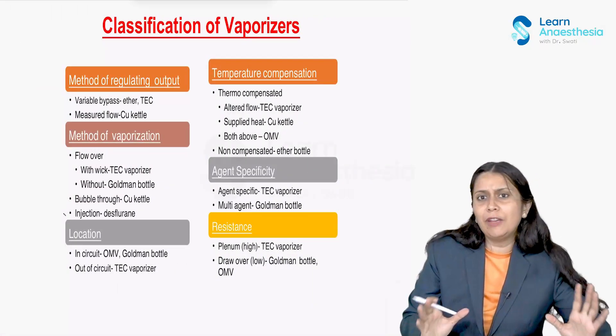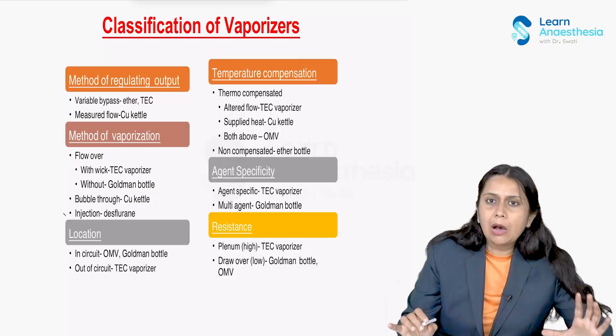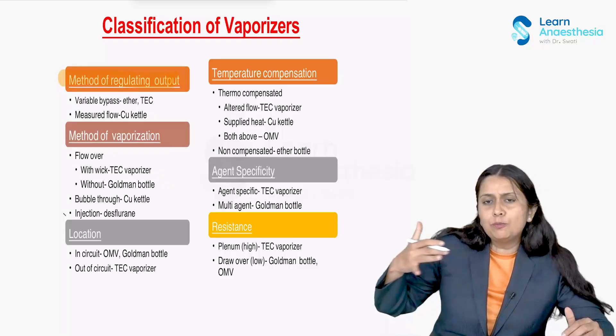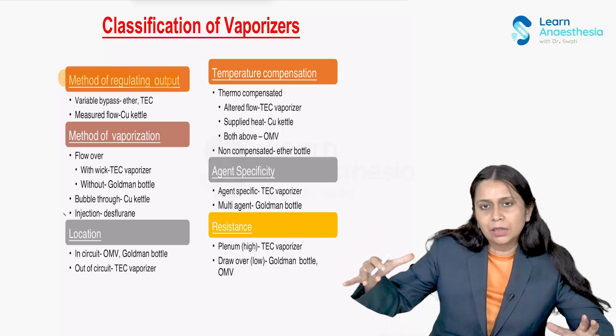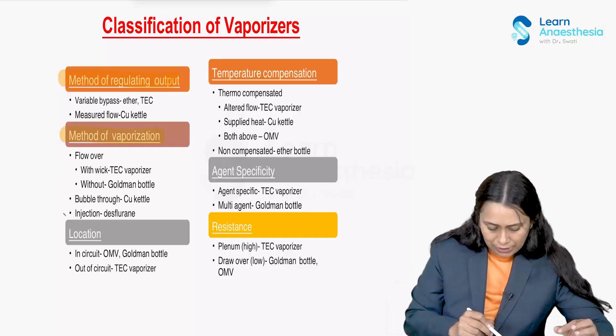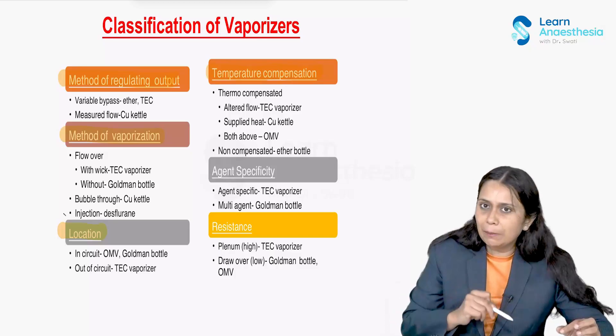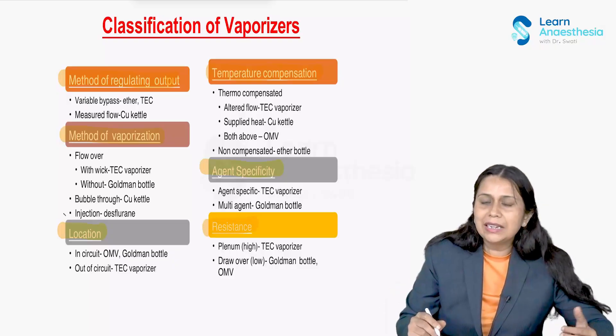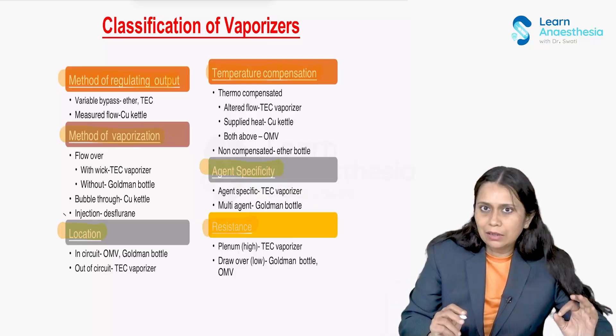How do we classify the vaporizer? Vaporizers are classified on six important points: first, the method of regulating the output — how the vapor is added and how much; second, the method of vaporization; third, where it is located — in-circuit or out-of-circuit; fourth, whether it is temperature compensated or not; fifth, whether it is agent-specific or not; and sixth, whether it has high or low resistance.